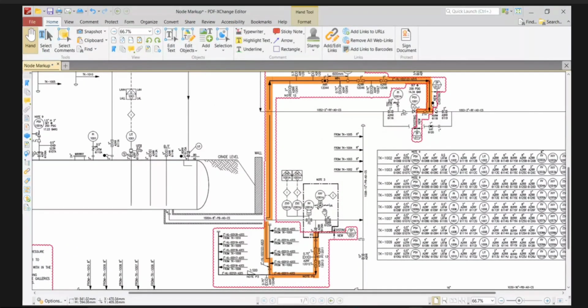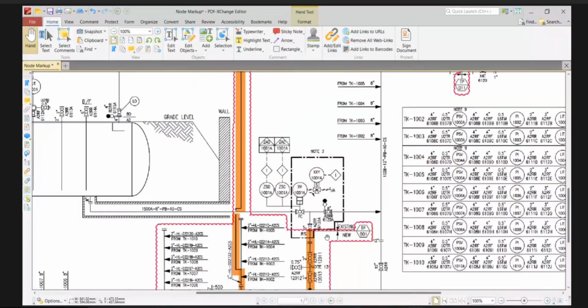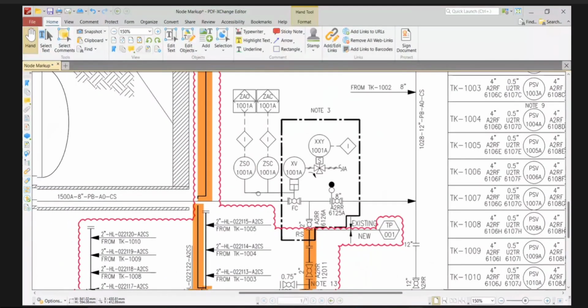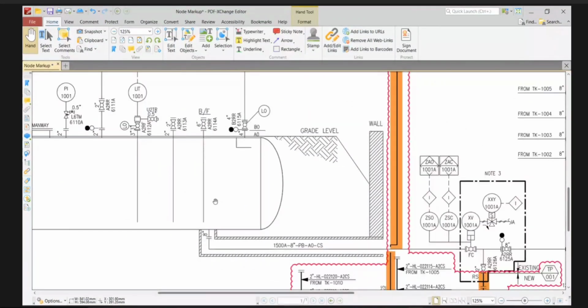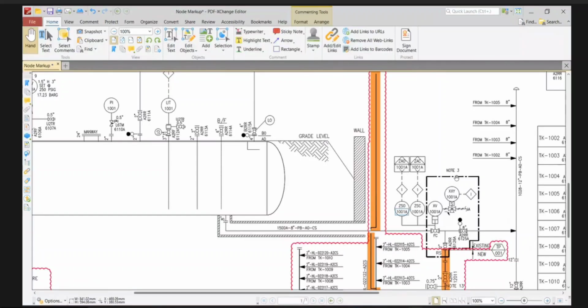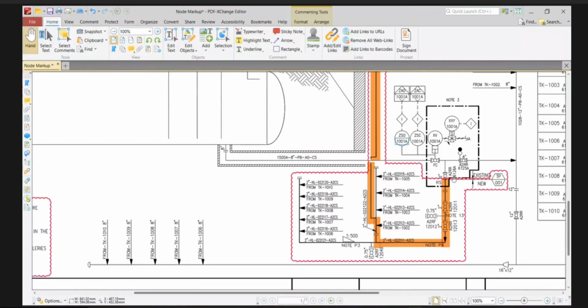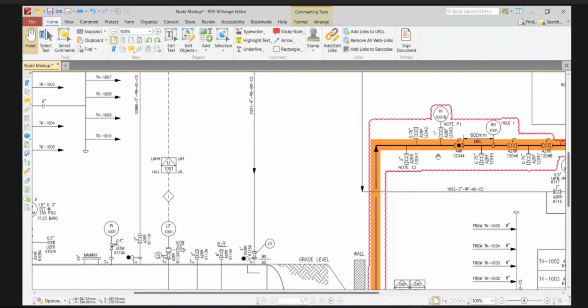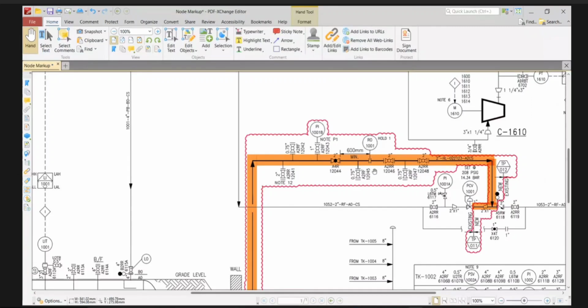If you see here, I will have two options here. Since this is the planned activity, the operator has to open the valve after ensuring that entire liquid has been blown down, has been removed from this proposed tank to other bullet, and after that, this valve will be opened, and there are many valves. This is the main valve. There is a block and bleed, and after that, it will come here 12044 valve, and then we have RO, then we have downstream two valves.